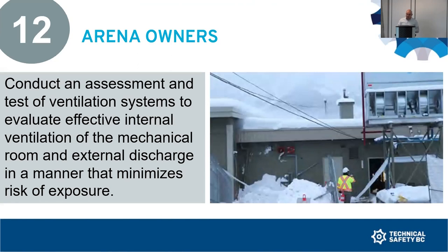But it also needs to be done whenever there's been any kind of renovation work, construction, equipment upgrading, or any other building changes that may influence the flow of air and the ventilation within the facility. So this test, as Jeff mentioned, can be conducted easily and quite cost effectively. One can get a smoke candle, light the smoke candle, watch where the air goes, and see what happens. As contractors and mechanics, it's up to you to recommend changes if the tests prove that the ventilation system is not working adequately and is not ventilating the building, and discuss with the asset owner, with the owner of the arena, what to do and how to improve the ventilation system. So if there is an incident, it will not be compounded by having flow of gases into enclosed areas. Now, let me pass it back to Jess.